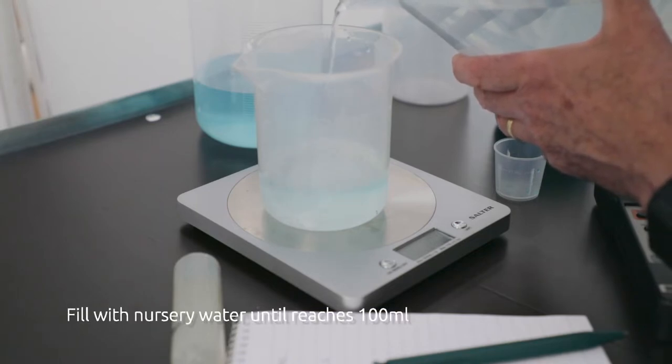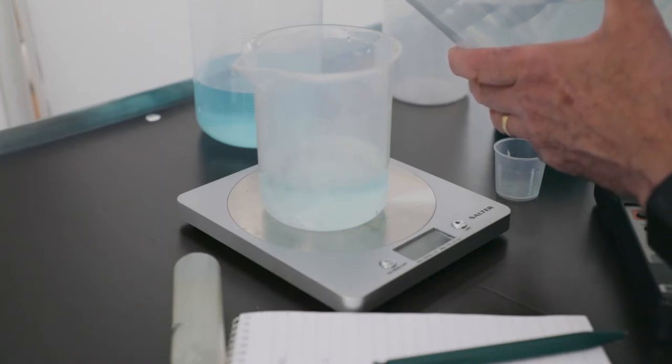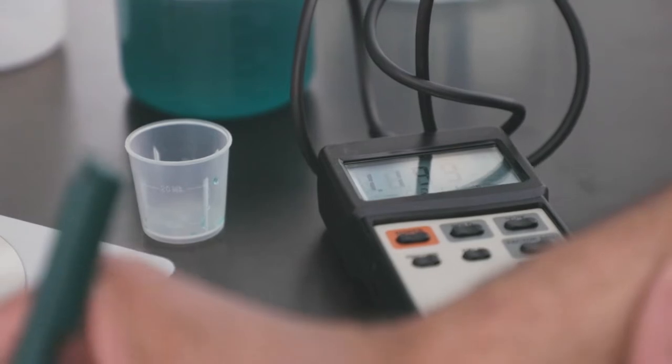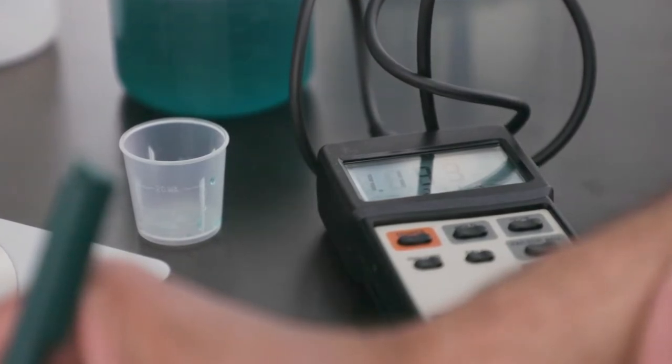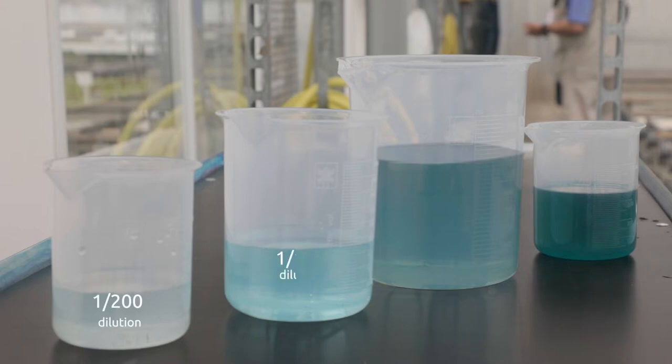And then similarly to last time we make a measurement of that one in two hundred diluted solution which would be our third calibration point. And this time we're getting a reading of one thousand one hundred and ninety three microsiemens. So we now have the third point for our calibration curve.